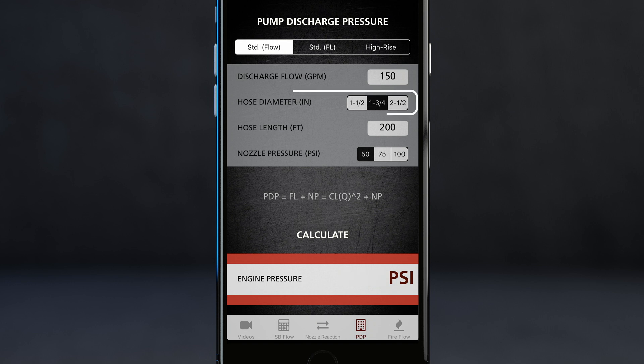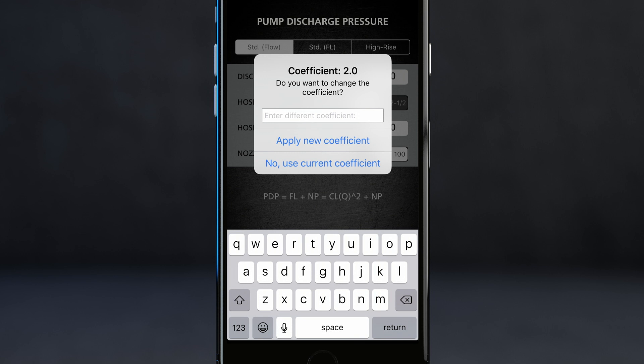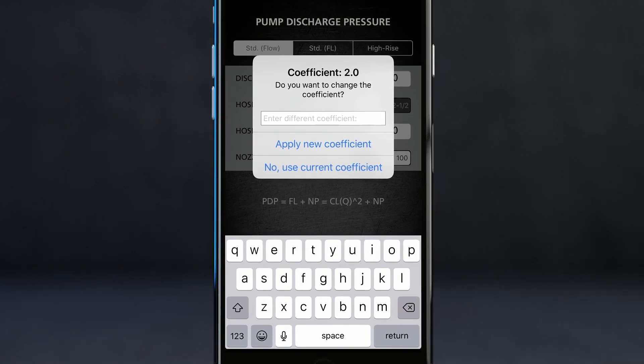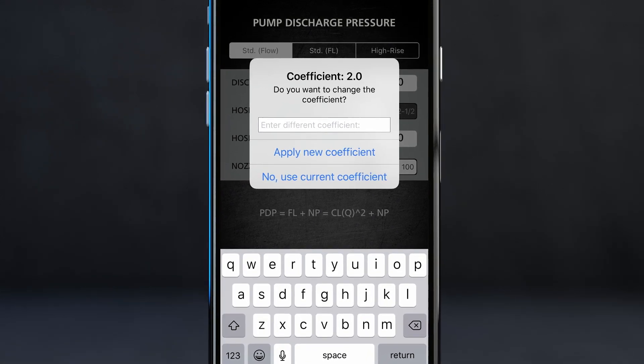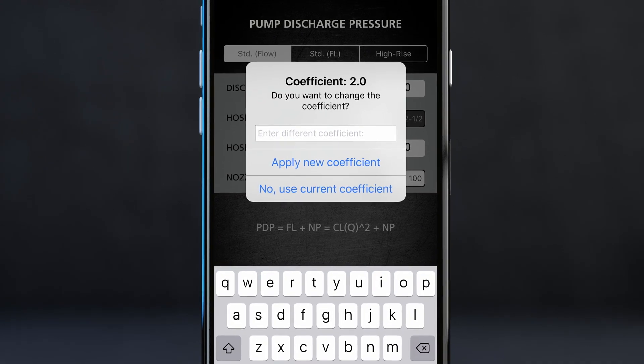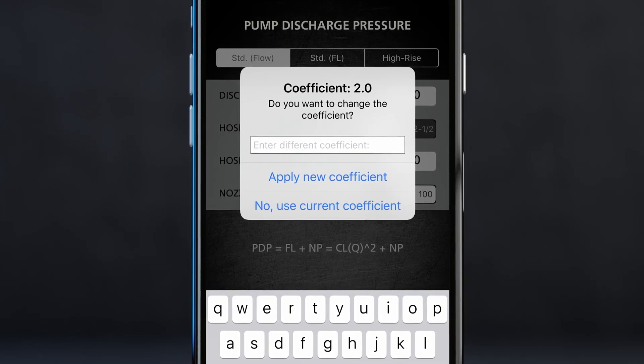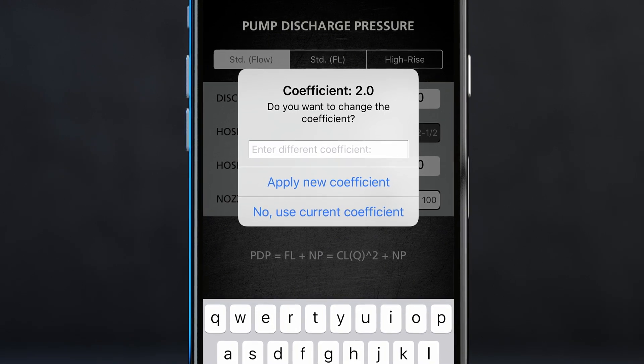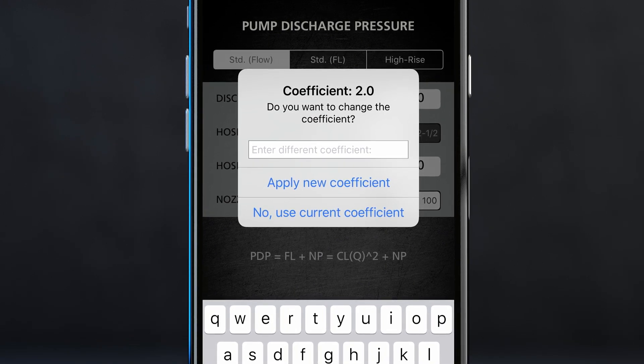If I change any of the hose diameters — for example, I go to 2½ inch — I'm asked if I want to change the default coefficient. All these formulas are based off default coefficients. So if you have different inside diameter hose and you know that coefficient, you can enter it in and apply the new coefficient, or use the default. This is helpful for users using two-inch hose, which can have several different coefficients based on 1½ inch or 2½ inch couplings. If you're using two-inch hose and you know that coefficient, here's where you would be able to use the app.